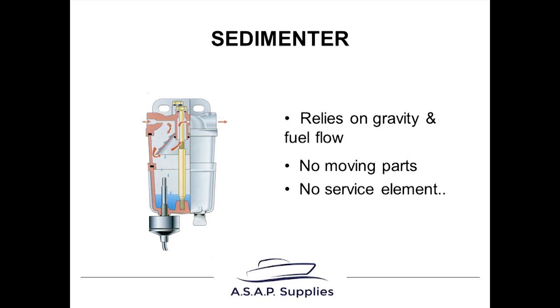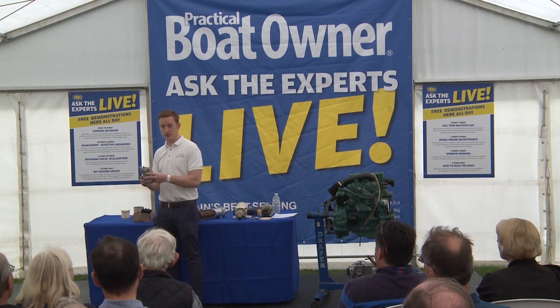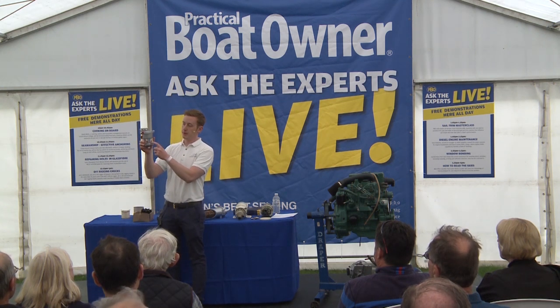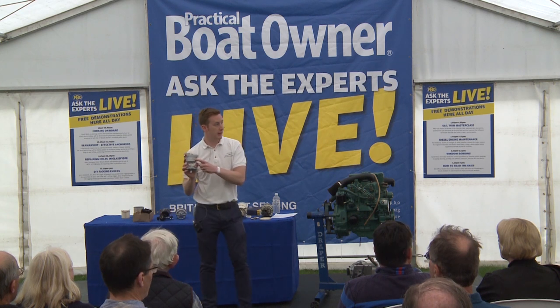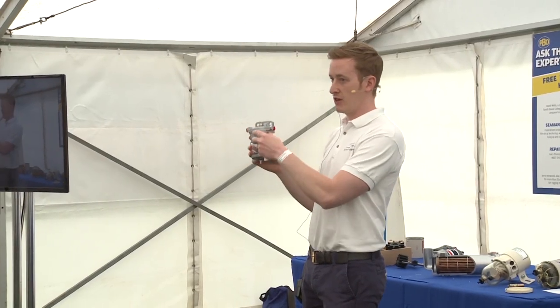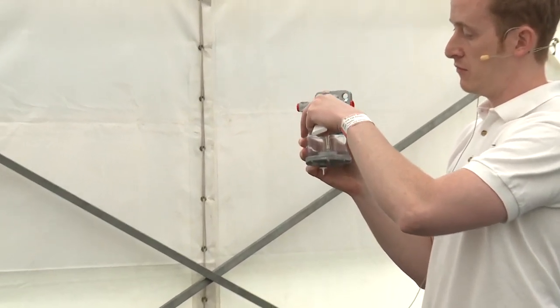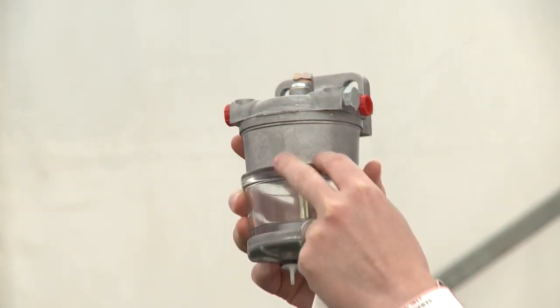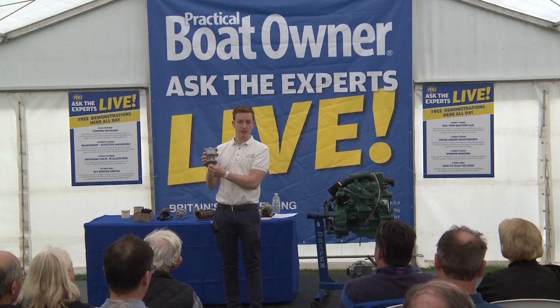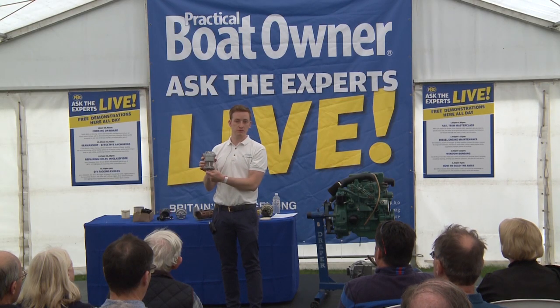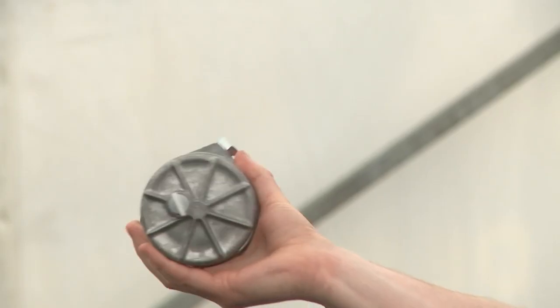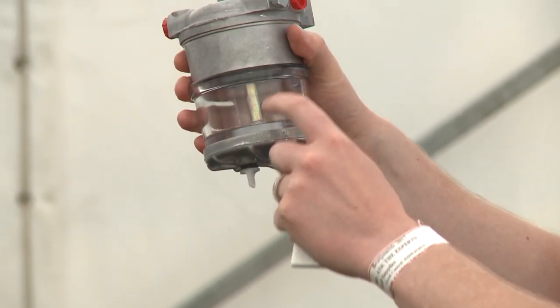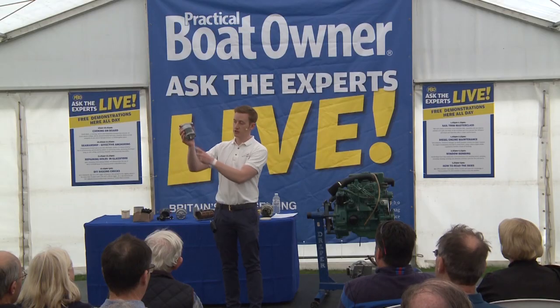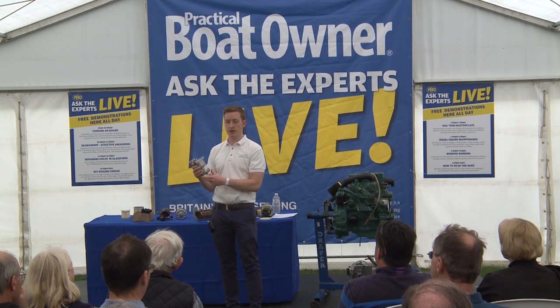So we start off with the most basic, a sedimenter. We've got one here. It will generally look something like that - a glass bowl at the bottom, and inside there's that cone looking part. Fuel comes in and it relies on gravity forcing the water out of the fuel. It forms droplets and ends up in the bottom of the bowl. There's actually no service parts to take out on a yearly service. We'd just recommend cleaning it out and regularly checking how much water's in the bottom there. You can just drain it out at the bottom. Very straightforward.